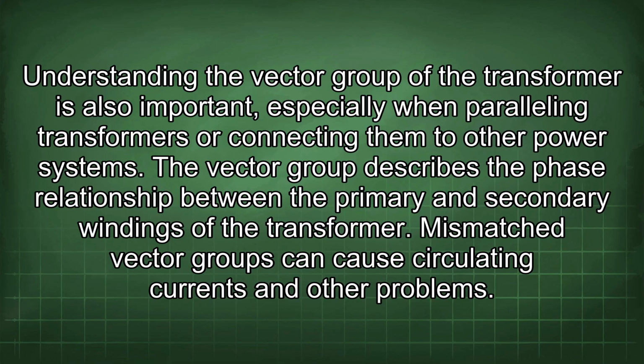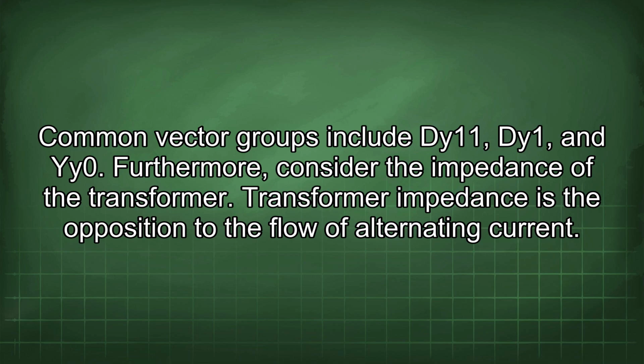Understanding the vector group of the transformer is also important, especially when paralleling transformers or connecting them to other power systems. The vector group describes the phase relationship between the primary and secondary windings of the transformer. Mismatched vector groups can cause circulating currents and other problems. Common vector groups include Dyn11, Dyn1, and YNyn0.